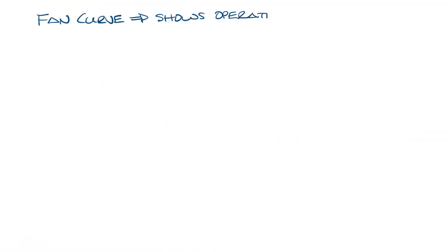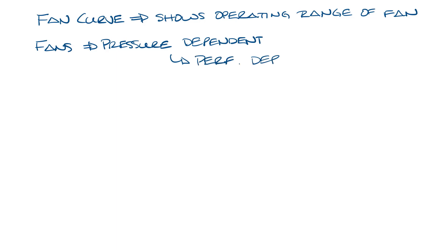So the fan curve shows the operating range of the fan. Fans are pressure dependent, which means that their performance depends on what pressure they're operating against. The airflow, or CFM, is dependent on the static pressure that they're working against. So as pressure goes up, airflow goes down.